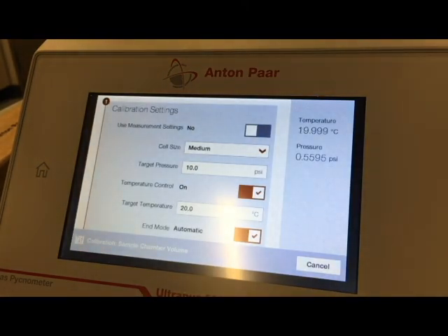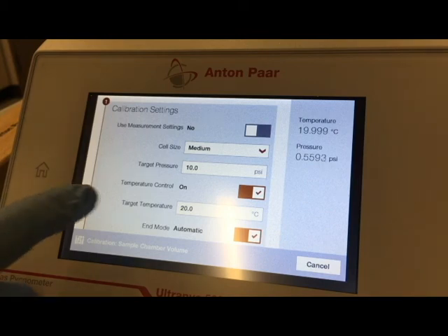Temperature control, we have a range between 20 degrees and 50 degrees Celsius. If you do not wish to have any unusual temperatures or to see the heightened temperature of your sample, choose 20 degrees Celsius, as that is typically the room temperature in our lab. If you want to go any higher, please allow at least 20 minutes for your sample to sit in the instrument between the calibration and the run in order for your sample to come to a temperature equilibrium. We're going to just run this powder at room temperature right here, so we're going to leave it at 20 degrees.